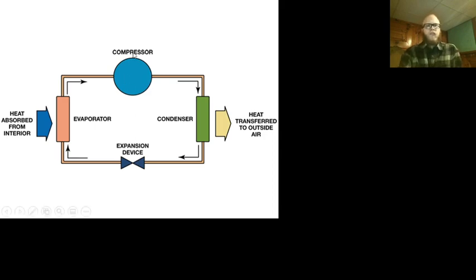So I had a student, I think the first year I ever taught anything about refrigeration, looking at a chart similar to this, and he said if you draw a line between the compressor and whatever your restriction is, then you can see what's your high side, right, between the compressor and the restriction, and then the low side between the restriction and the compressor, because on the low side, the compressor's pistons are moving down, trying to draw in that vapor refrigerant. So low pressure over here, just like the ground side of an electrical circuit.